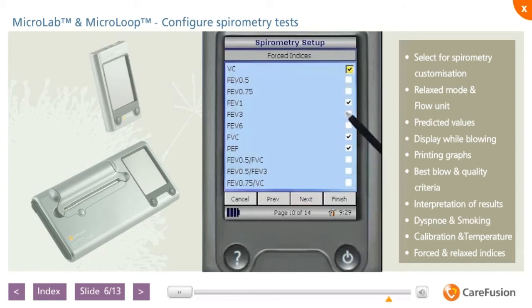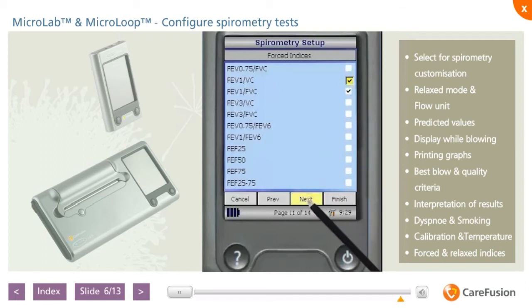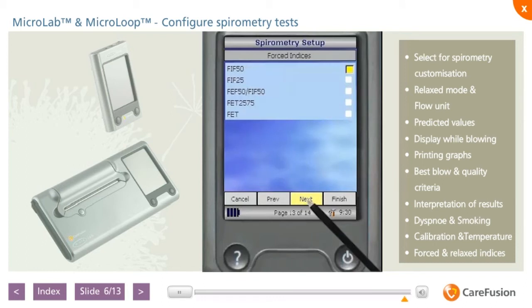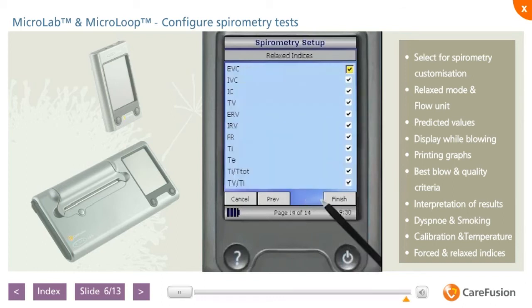The indices to be displayed can be selected from the list shown for both forced and relaxed maneuvers. All indices are measured and recorded on the spirometer. However, only those selected on these screen menus will be displayed and printed together with the test results. Further indices can be added to the test by going back and selecting them if the test has been saved. To proceed through the list, select Next. Once you've made your selection, press Finish to return to the main menu.